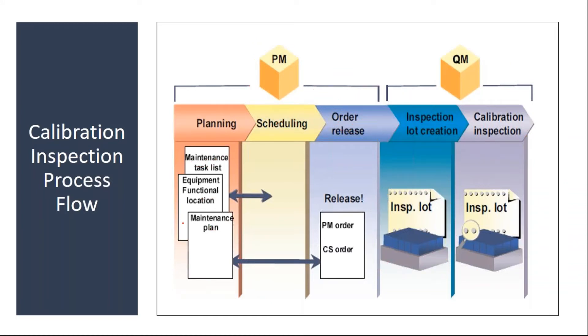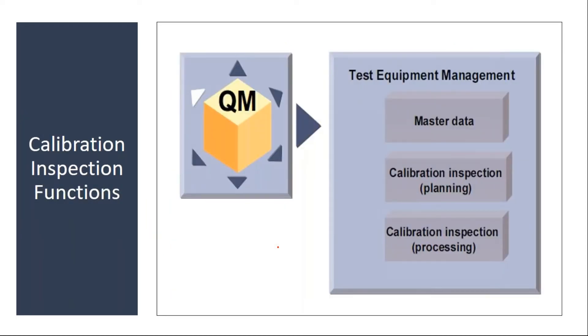So basically it is an integration between PM and QM modules. You need to coordinate with your Plant Maintenance consultant, as most of the master data will come from the PM side. In this calibration inspection function, first we will be creating all the master data required, then the calibration inspection planning activity, and then the processing — once the order gets generated along with the inspection lot, you will do the processing of the calibration inspection.